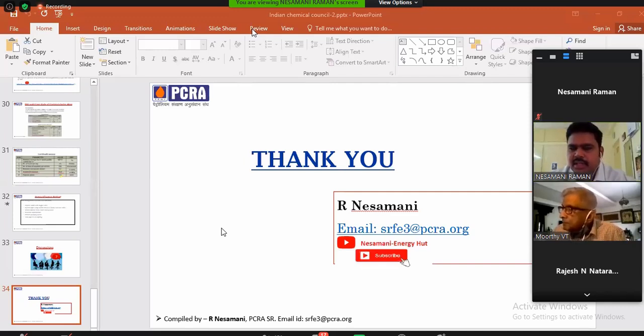At present, we are able to produce 85 degrees Celsius, sir. That is what we are giving to the process boiler now. We designed the VAM with the Thermax designer for around 80 degrees Celsius. In the VAM itself, we put one more additional heat exchanger with steam. If we are not able to attain 80 degrees Celsius, some amount of steam will go and increase the temperature to 80 degrees Celsius, so that at any point of time we can meet the design temperature of the VAM.